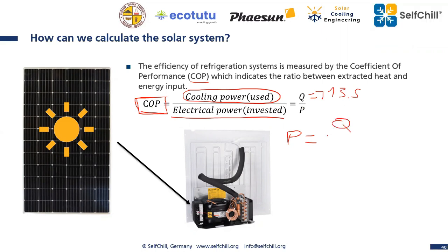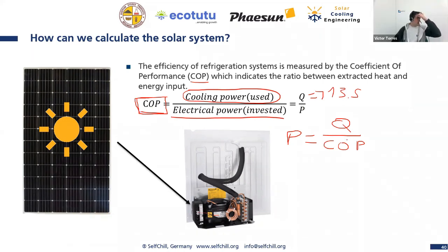We need... sorry, I think it is 15.7, not 13.5. Exactly, we calculated 15.7, but because of my calculation on the next slides, I'm using 13.5. I kindly request for all of us to consider the cold cell with 100 millimeters. If you remember, it had 2 kilowatt hour per day less thermal load, so that we come to the 13.5 kilowatt hour. I need to do it like this because all my calculations in the next slides are based on this value.